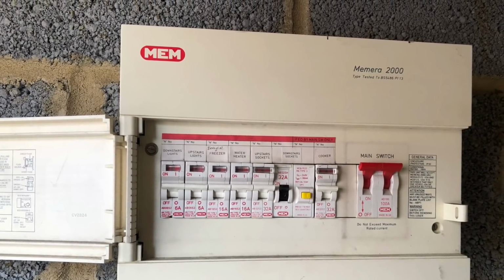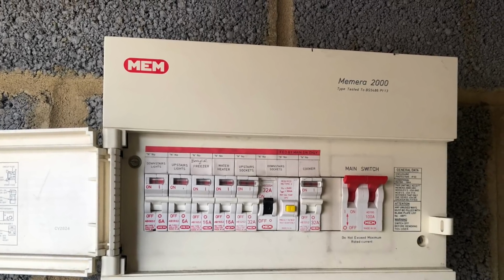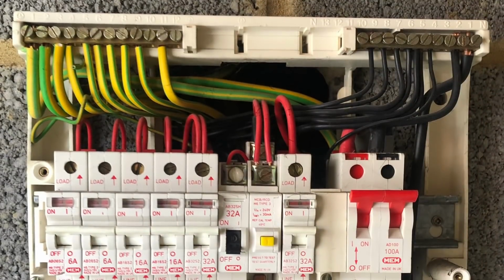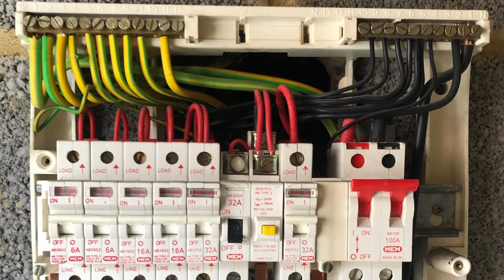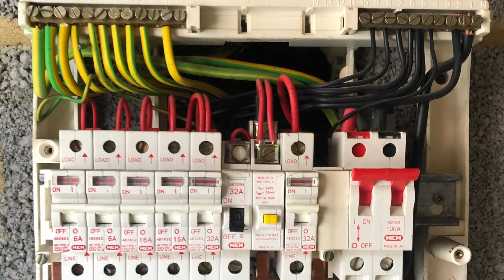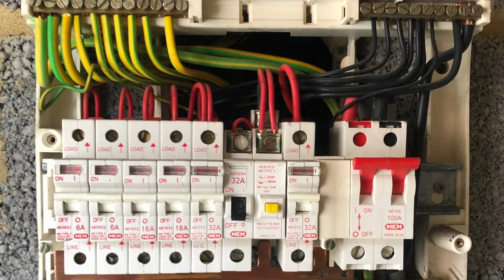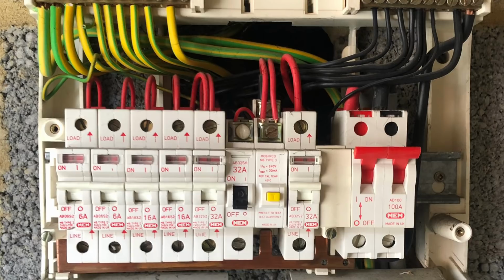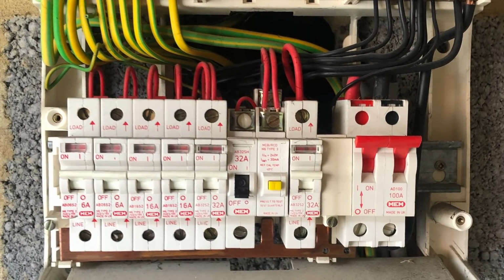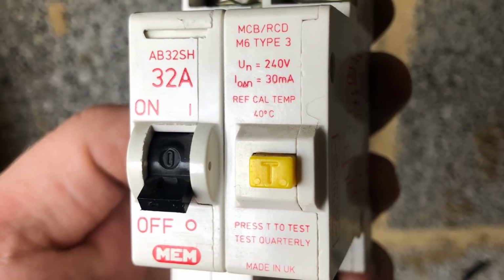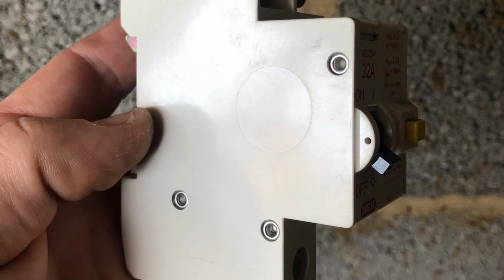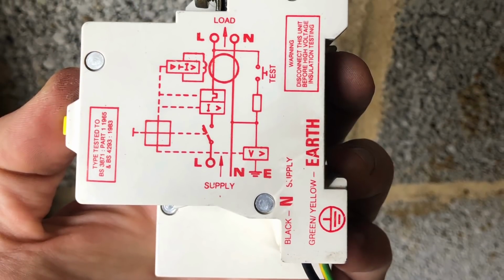So that was the next job that I did. So here's the consumer unit. Nothing particularly untoward about that. You can see that RCBO in the middle. And as we take the cover off, well, it all looks nice and neat, but wait, something's not right. Can you see it? The functional earth is not connected for the RCBO. That was a red herring, unfortunately, because that was not the problem. It turned out it was this RCBO that was faulty. So I will probably be replacing that with a new one supplied by Uncle Phil from Circuit Breaker Specialist.